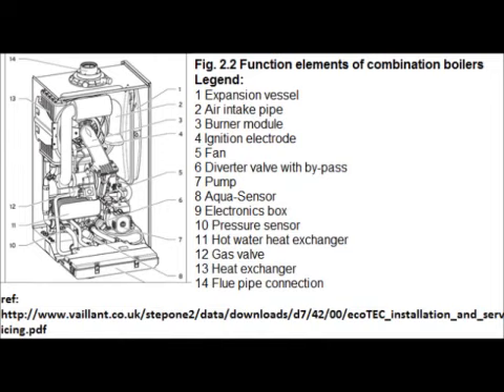Simple as that. Next thing we have is the burner module. After that we've got the ignition electrode — all that really is, is to ignite the flame, or ignite the gas, so that we can have a flame and have hot water, central heating, and such. The next thing on the list is the fan — in this case we have a zero governor. What is a zero governor? Unfortunately there isn't enough time in this video to explain the fan.